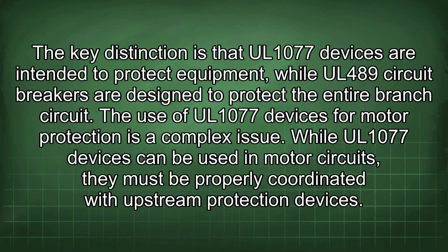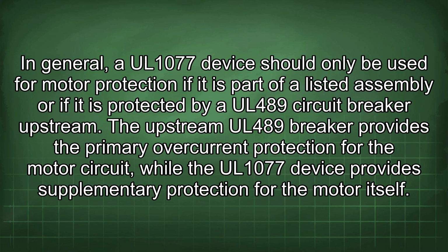The use of UL 1077 devices for motor protection is a complex issue. While UL 1077 devices can be used in motor circuits, they must be properly coordinated with upstream protection devices. In general, a UL 1077 device should only be used for motor protection if it is part of a listed assembly or if it is protected by a UL 489 circuit breaker upstream. The upstream UL 489 breaker provides the primary overcurrent protection for the motor circuit, while the UL 1077 device provides supplementary protection for the motor itself.